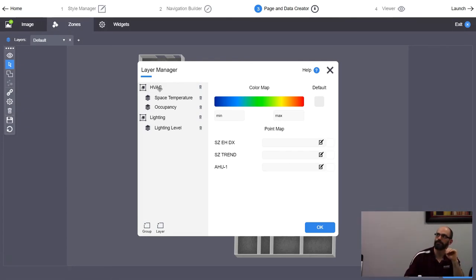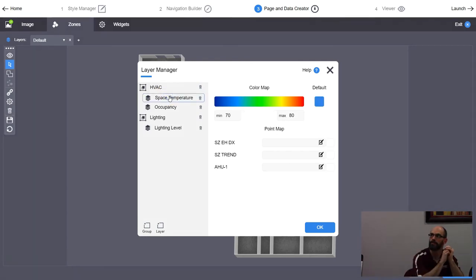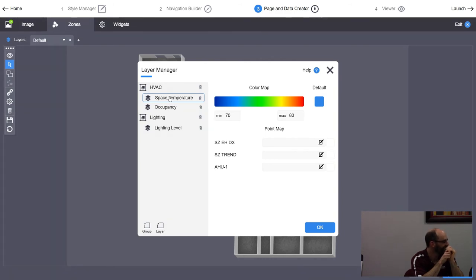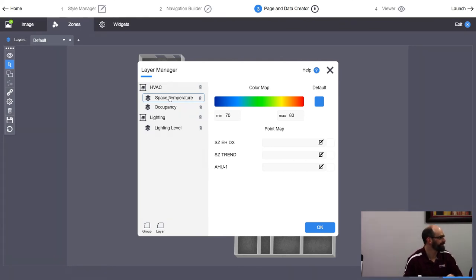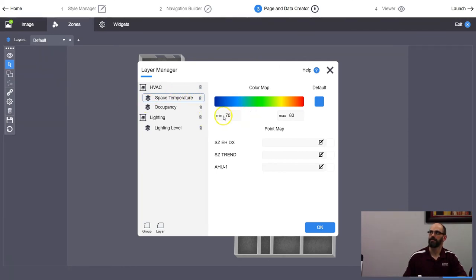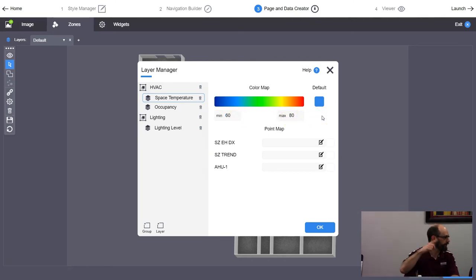The layer group defines which set of boxes you're drawing. The layer inside the group defines what value is associated with those boxes — cooling capacity, heating capacity, space temperature, humidity, CO2, whatever you want. The group layer is the box; the data layer is the value. I'll pick the Space Temperature layer first. Set min to 60 and max to 80 — the sine wave generating space temp runs 60 to 80, so that's a good range.